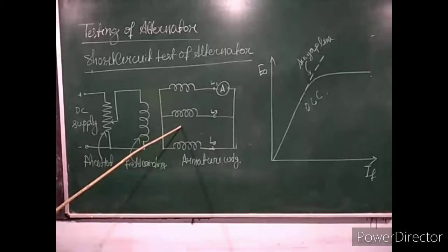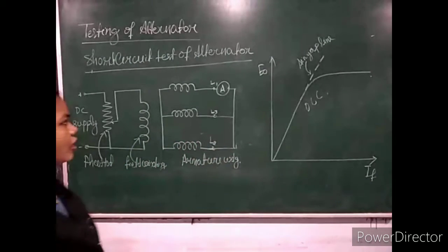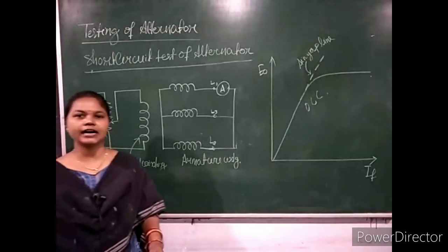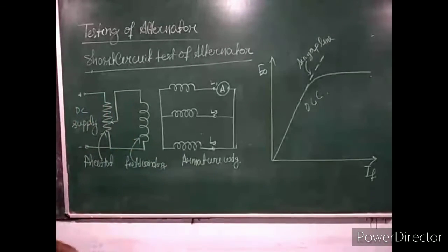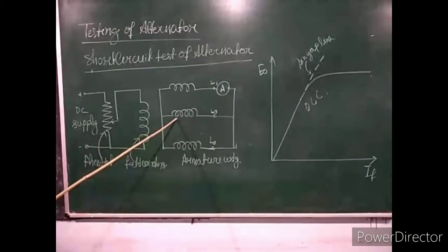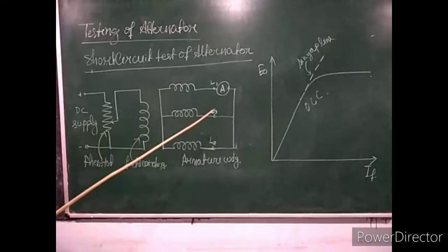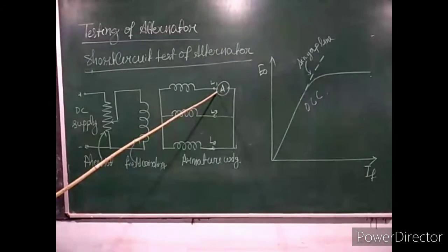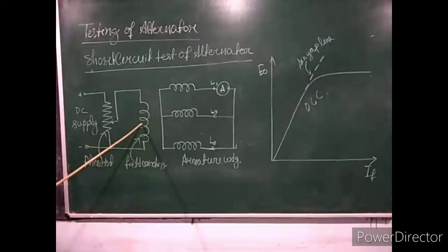What do you mean by a balanced system? A balanced system means all the line and phase quantities are equal. So here, since all three currents will be equal, only one ammeter is connected in any one of the three phases. A high value of rheostat is connected in the DC field circuit to vary the field current. The machine is run at synchronous speed.